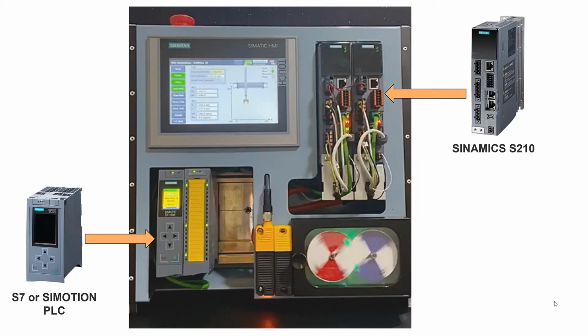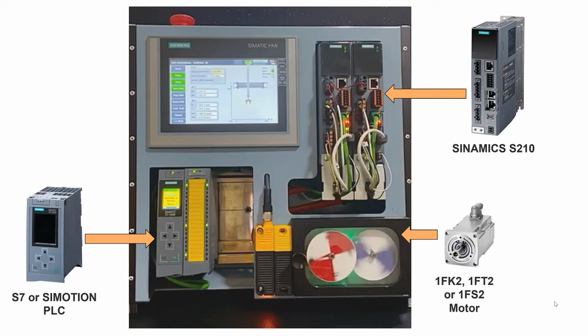A SIMATIC S7 or SIMOTION PLC is used to control the positioning functionality via Profinet or ProfiSafe. The PLC also helps set certain parameters for the S210 during setup, such as telegram selection and I/O configuration. SIMOTICS S-1FK2, S-1FT2, or S-1FS2 motors are specifically designed for the S210 system.